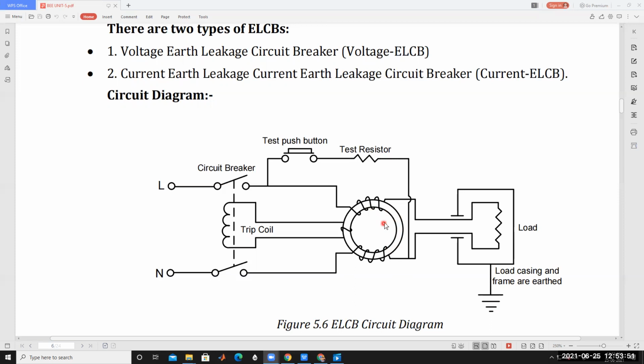CBCT is the current transformer. From the phase, that means the line, the line is connected in series with this core. From the phase wire it is then connected to your device, for example a TV, fan or fridge, whatever it may be. This is called the load, and the load's second terminal is the neutral. This wire returns back to the supply like this. So one side of the phase is connected in this way through the current transformer.